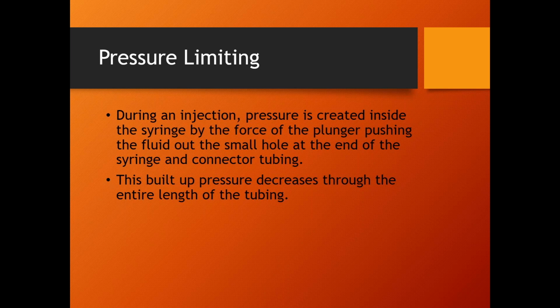So that pressure limit, and again, that pressure limit is not a goal, okay? What the pressure limit is designed for is so my syringe doesn't rupture during the actual injection. It is a patient safety thing, but it's not really for the patient, it's for the syringe. We're saying don't exceed 300 PSI because that will keep the syringe, hopefully, from rupturing during the actual injection. And they're rated at 400 PSI. Another thing I don't think I mentioned: syringes are one-time use only. They use it on one patient and then throw it away. There's a couple of exceptions, but they're special cases. So it's not like the syringe is going to get old and eventually wear out.